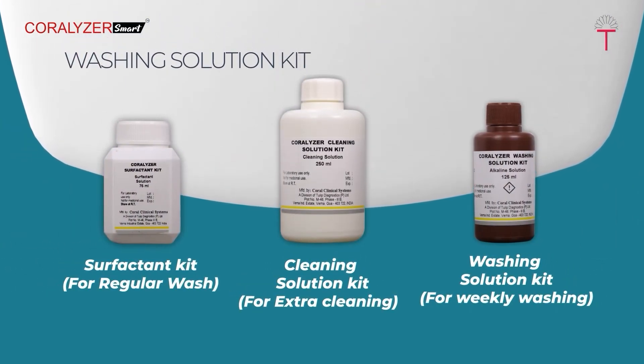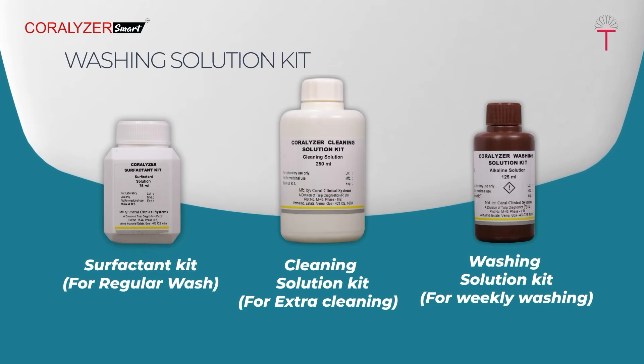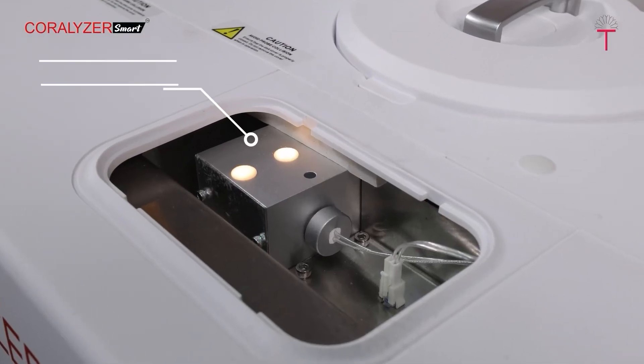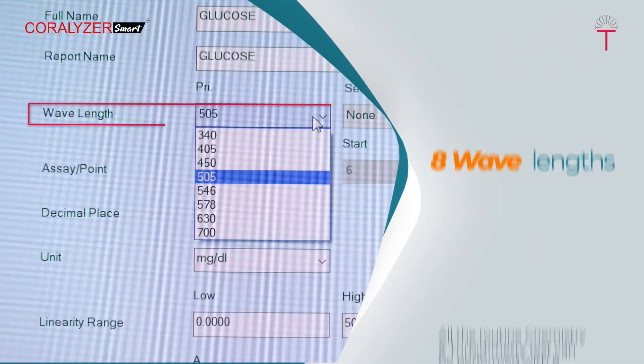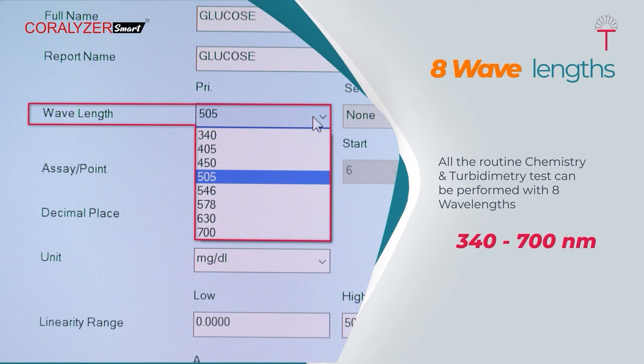Coralyzer Smart comes with dedicated system-pack reagents designed specifically for it. The maintenance solution kit — comprising surfactant cleaning solution and washing solution — helps in cleaning and reducing carryover caused by the build-up of proteins and latex particles. The light source used is a halogen lamp for longer life; it is easily accessible and can be replaced without opening the instrument hardware.